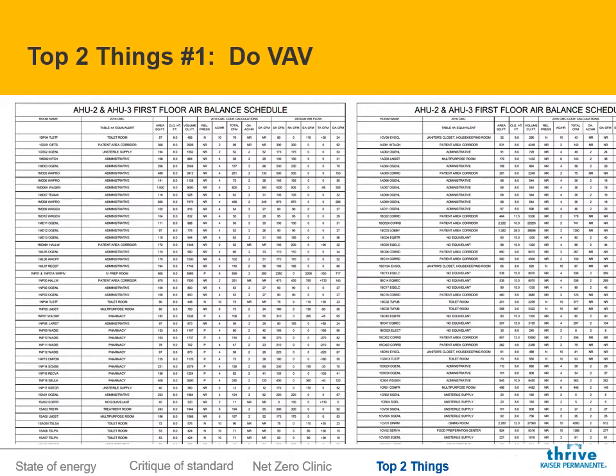Now, if we were electrical engineers, we'd be shot for proposing a lighting design where all the lights run 24/7. But in hospital HVAC, we do this all the time, man. And remember that the biggest use of energy that we have in hospitals is reheat. And in ASHRAE, we know how to get rid of reheat. It's called VAV. And in every other building type outside of hospitals, it's required by Title 24 and ASHRAE 90.1, and we've been doing it for years. Off hours, you reduce the air. Even during hours, you reduce the air down to the code minimum before you turn on the heat. So you've got to reduce to code minimum, right?